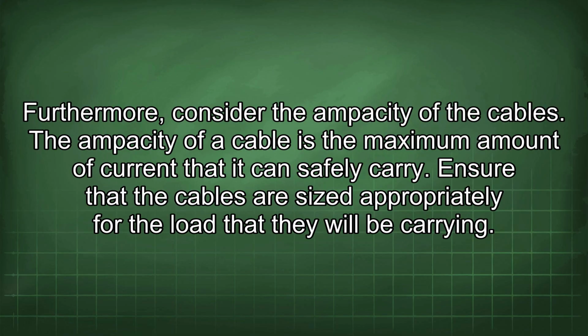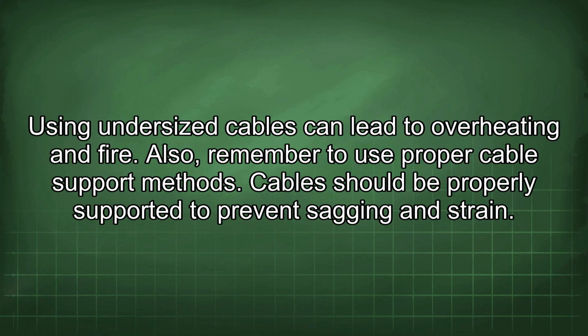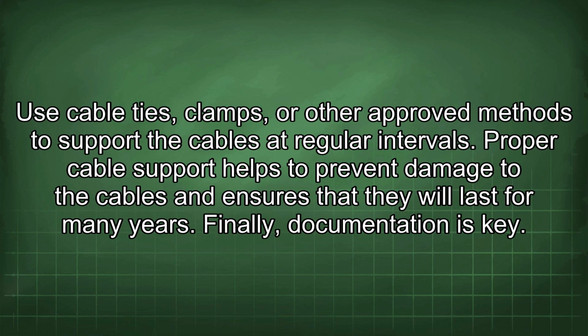Furthermore, consider the ampacity of the cables. The ampacity of a cable is the maximum amount of current that it can safely carry. Ensure that the cables are sized appropriately for the load that they will be carrying. Using undersized cables can lead to overheating and fire. Also, remember to use proper cable support methods. Cables should be properly supported to prevent sagging and strain. Use cable ties, clamps, or other approved methods to support the cables at regular intervals. Proper cable support helps to prevent damage to the cables and ensures that they will last for many years.